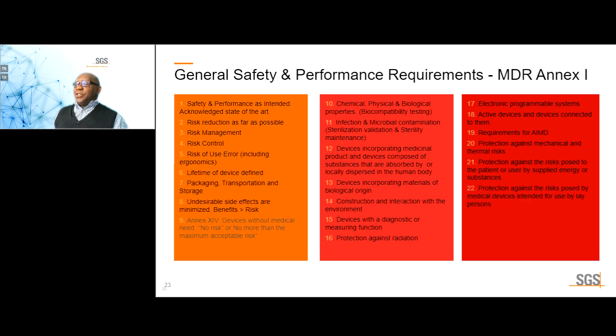GSPR 17, 18, 19, 20, 21, 22, and 23 complete the list. 23 is information supplied by the manufacturer, and it has 4 paragraphs. 1 is the general requirements. That's 23.1. 23.2 deals with the labels. 23.3 deals with information for products for which sterility has to be maintained, and 23.4 talks to the IFU. 23.4 in itself has subsections A to Z, and then goes on to AA and AB. So I'm just trying to illustrate how extensive these GSPRs are.